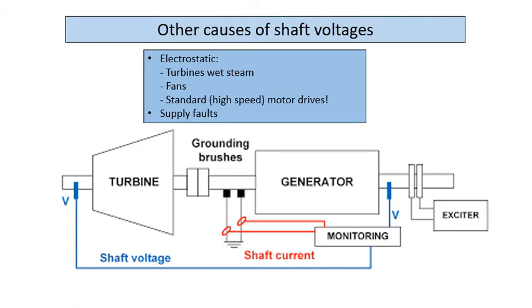Well, this is self-explanatory. The causes of shaft currents are the fact that a shaft voltage exists, and you need a current path, and you need that current path to be closed. So ideally, to prevent the shaft currents, you've got to remove the shaft voltage. It's almost impossible. Or you break the current path, or you divert the current.